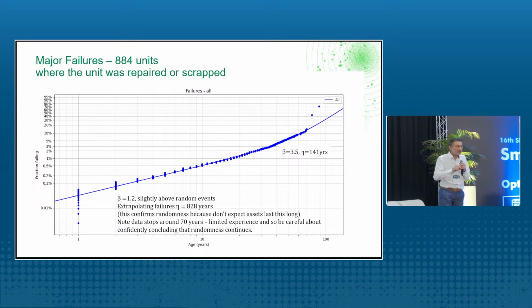But, of course, you have to check the condition of the individual transformer. So you need a condition-based maintenance instead of a time-based maintenance. Yeah, and this brings me almost to the second part of my presentation. So that is the reason we need condition diagnosis for transformers, because they fail more or less randomly.